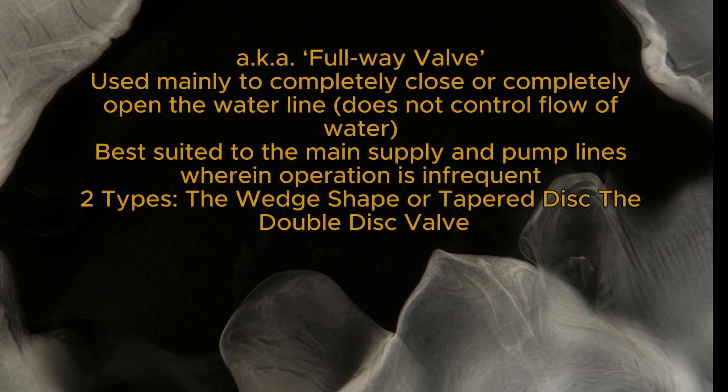The gate valve, also known as a full-way valve, is used mainly to completely close or completely open the waterline. It does not control the flow of water and is best suited to the main supply and pump lines where operation is infrequent. Two types: the wedge shape or tapered disc, and the double disc valve.